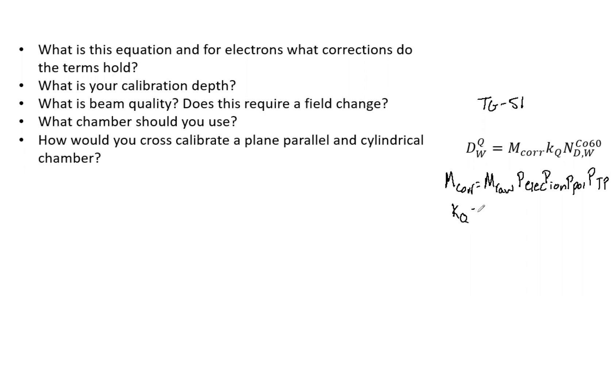KQ is going to be broken up into P-gradient, KE-cal, and K'R50. And then the absorbed dose to water calibration factor comes from ADCL for your chamber, and that is just a number.